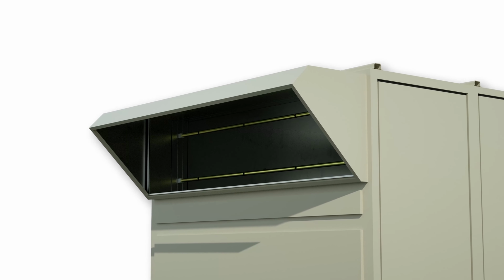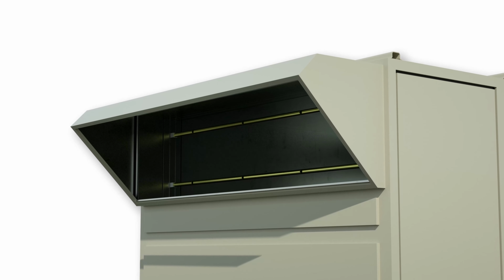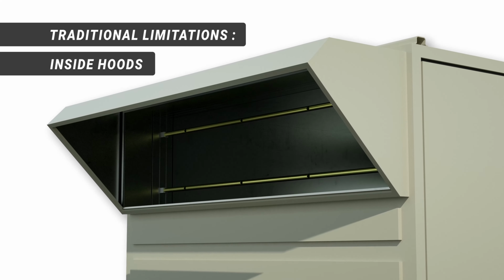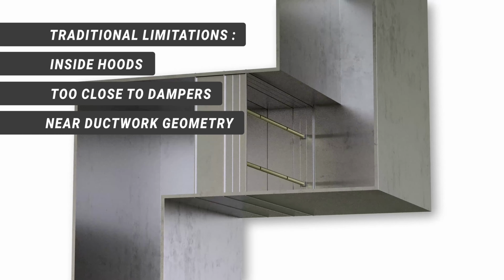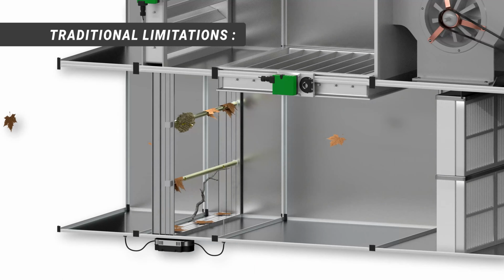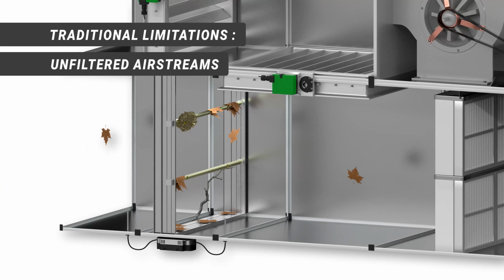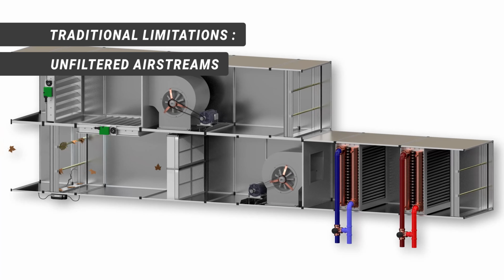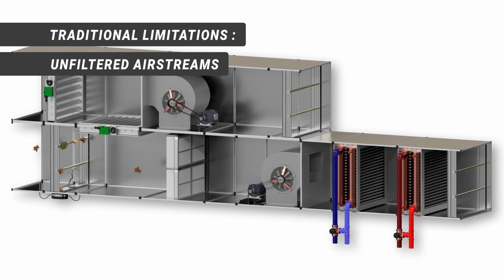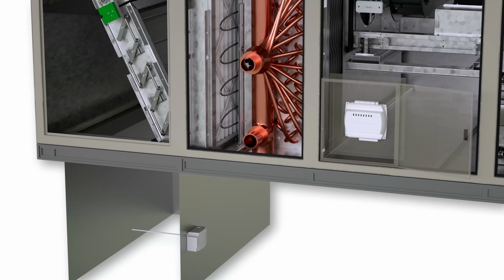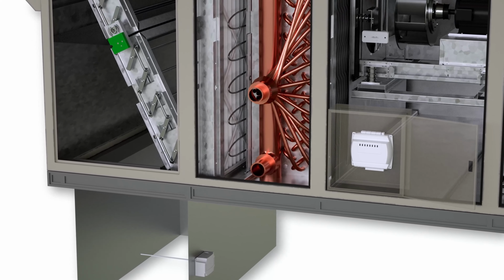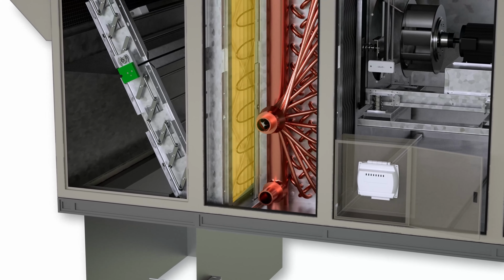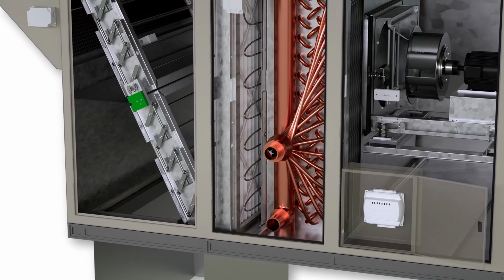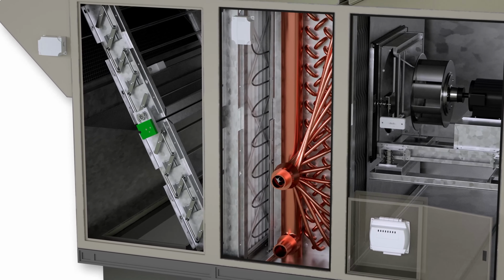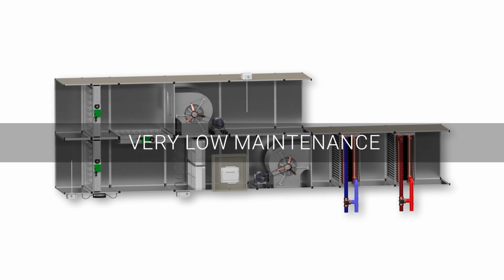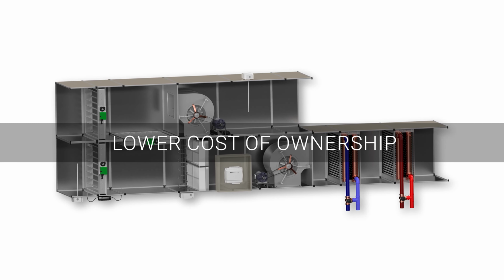Commonly, outside airflow measurement devices are installed in locations that aren't conducive to accurate measurements, such as inside hoods, too close to dampers, or near ductwork geometry that can cause turbulent conditions. Another common occurrence with traditional measurement devices is installation in unfiltered airstreams, causing measurement degradation over time and ongoing system maintenance requirements. The KMC AFMS senses airflow in the proper, filtered locations, with any sensors in the unfiltered airstream unaffected by dirt, moisture, and debris, meaning this solution upon installation requires very low maintenance. This leads to a lower cost of ownership.